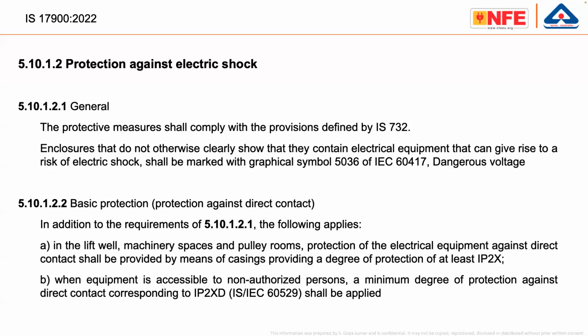The second para is actually additional. The enclosures, one moment, let me take the pointer. Yeah, enclosures that do not otherwise clearly show that they contain electrical equipment that can give rise to a risk of electric shock shall be marked with a graphical symbol. You see the danger symbol. So if that is not already clear, additionally, we should do that.